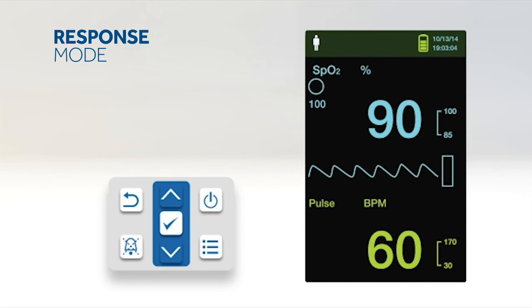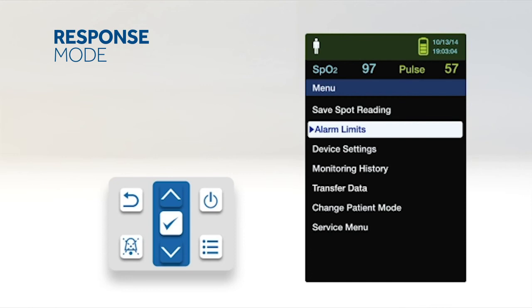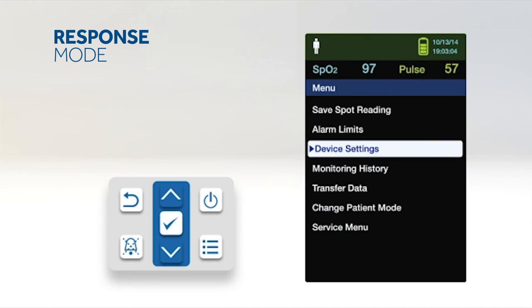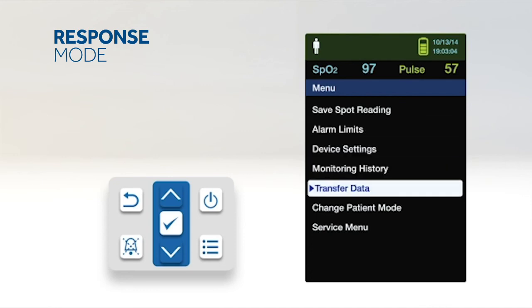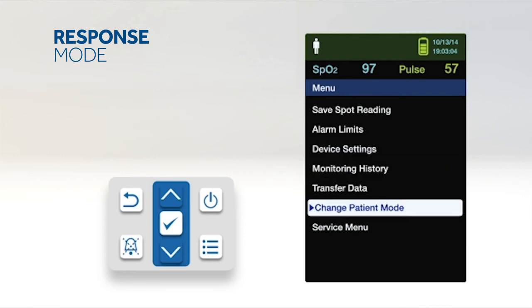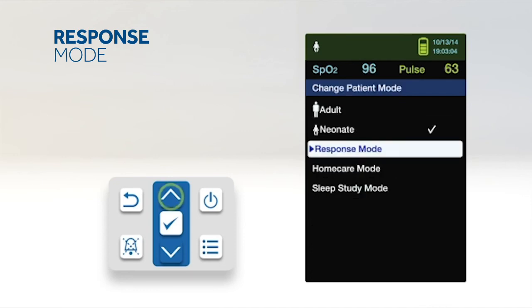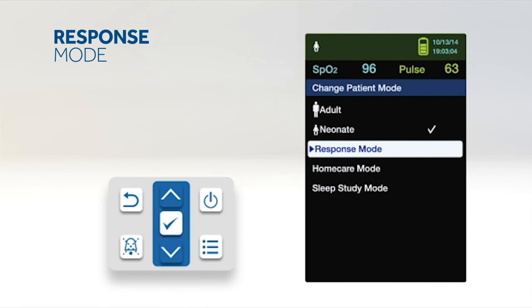Response Mode establishes the rate that the monitoring system responds to changes in SPO2 readings. To set the response mode, access the change patient mode menu. Press the up or down button to highlight the response mode menu, then press the OK button to select response mode.